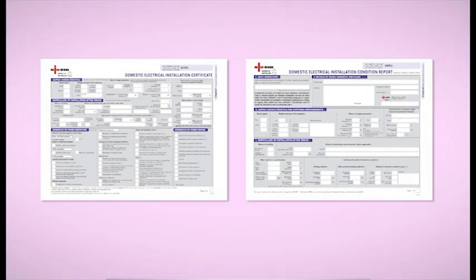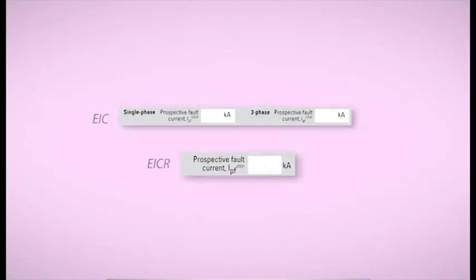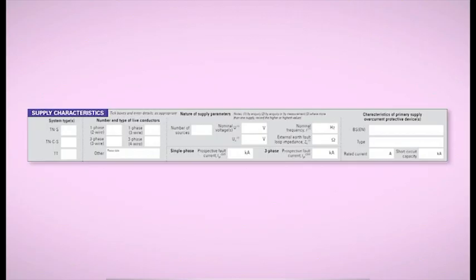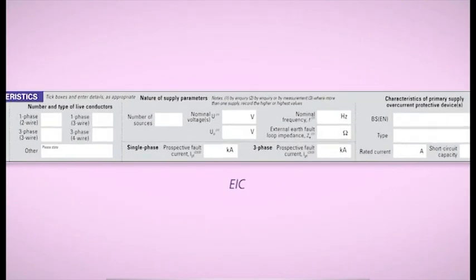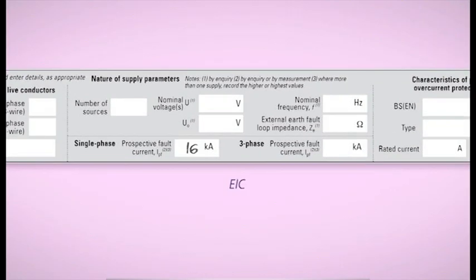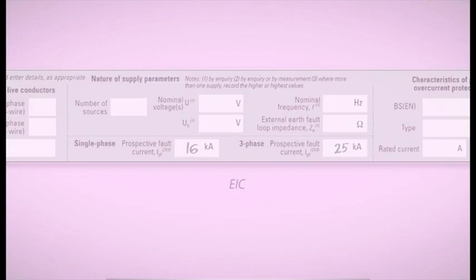by the regulations. The next thing to consider is prospective fault current. The forms do allow us to either determine this by inquiry or measurement. However, I would normally expect the boxes under supply characteristics to be filled in with the data from the design information. This, on most occasions, will be values determined by inquiry. Typical values are 16 kA for single-phase supplies and 25 kA for three-phase supplies.